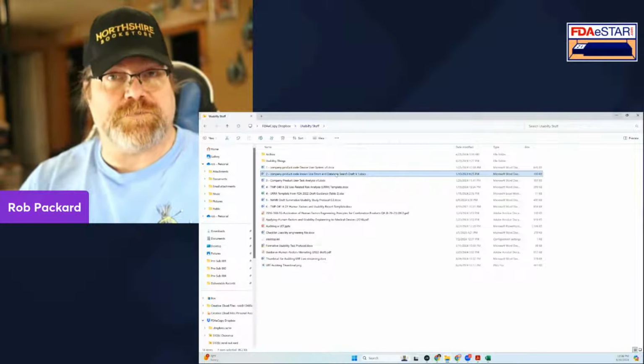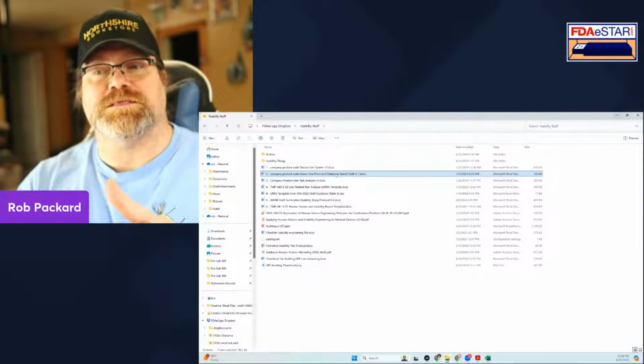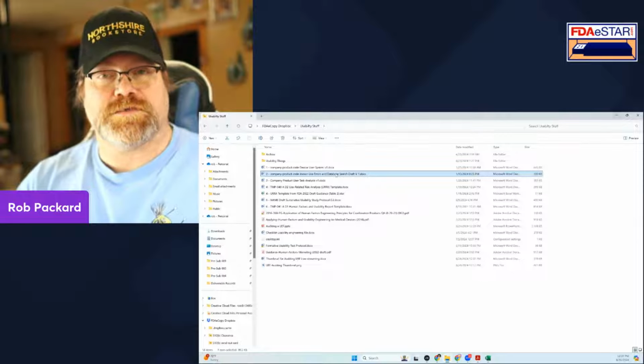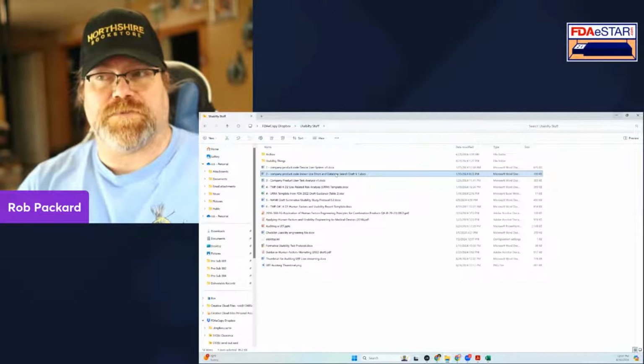If you don't, you might search what competitors had out there. What is your predicate if you're doing a 510(k)? And you would gather all that information and summarize it in a report. This is what we found for use errors that exist out there for the product.